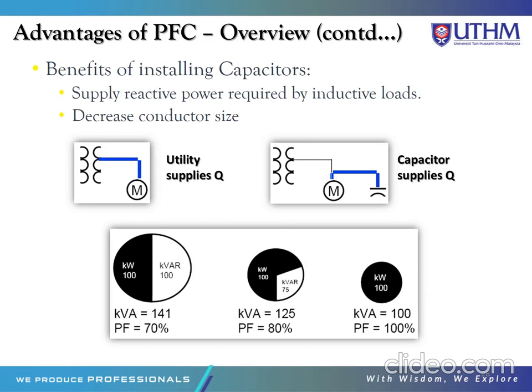Next we go to the advantages of PFC. There are two benefits. The first is that by installing capacitors, we can supply the reactive power required by inductive loads. The second is that it can decrease conductor size. This is the figure of the utility supply Q. We have Q here, and this is the load. This is the connection of how the capacitor is connected to the load. The capacitor is connected in parallel with the load.